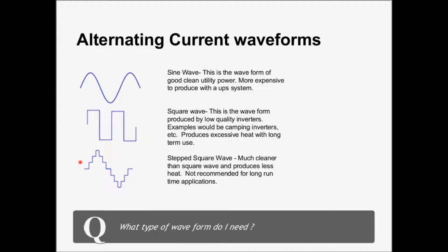So a step square wave is fine for a lower cost piece of equipment like a PC, and you don't want to run on it for a long time, generally more than 10 or 15 minutes at a time whenever you have an outage. And a sine wave is the ideal power output waveform, and more of the high quality UPS systems use that type.